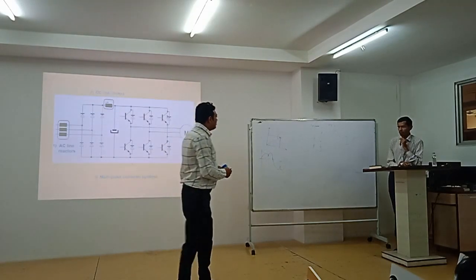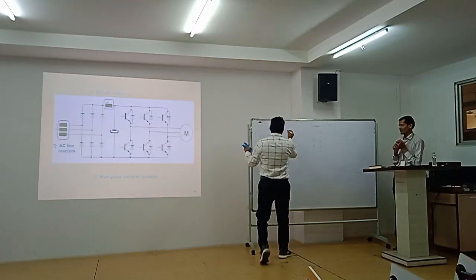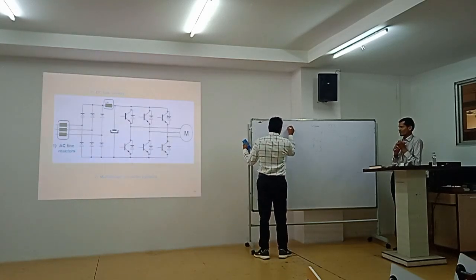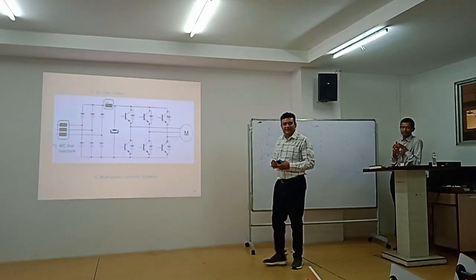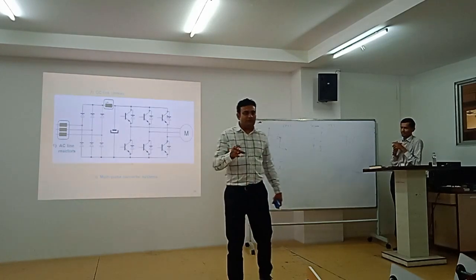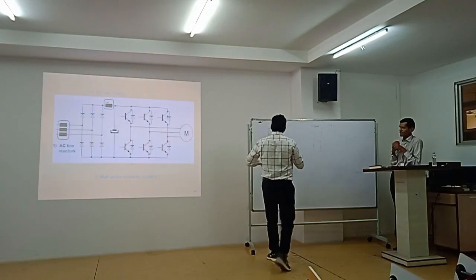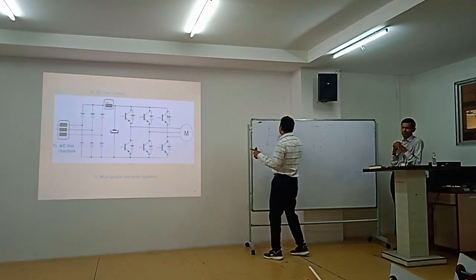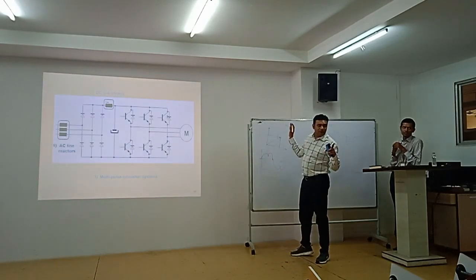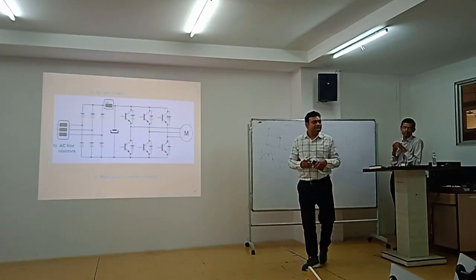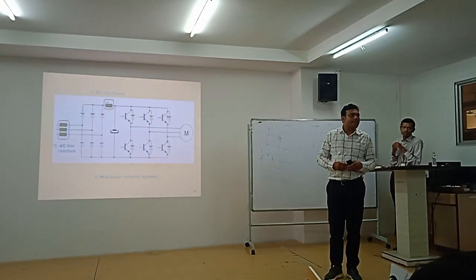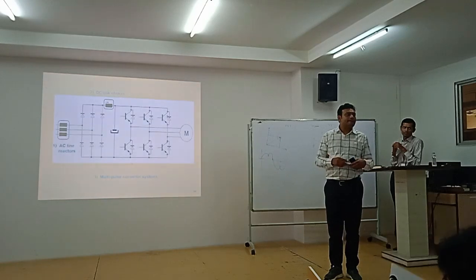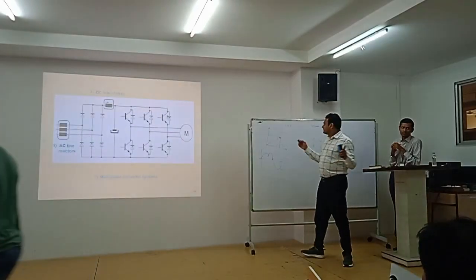So I think that's the formula, something like 6p plus or minus 1. Order of harmonics will be 6n plus or minus 1. So the first harmonics that will appear will be the 5th and 7th: 5, 7, 11, 13 and so on with 6 pulse.